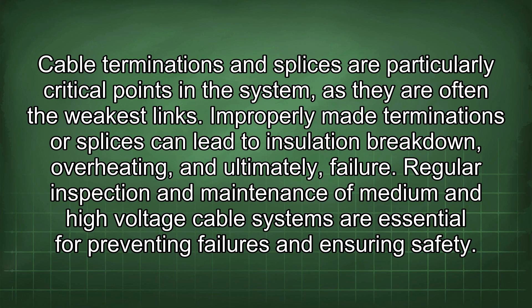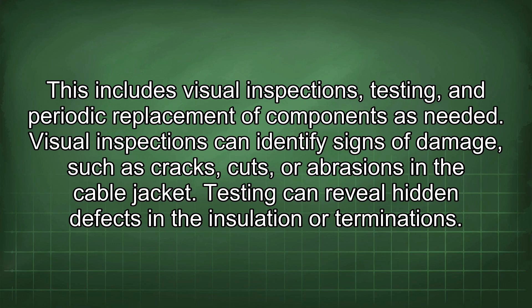Regular inspection and maintenance of medium and high voltage cable systems are essential for preventing failures and ensuring safety. This includes visual inspections, testing, and periodic replacement of components as needed. Visual inspections can identify signs of damage such as cracks, cuts, or abrasions in the cable jacket. Testing can reveal hidden defects in the insulation or terminations. Keeping accurate records of inspections, tests, and maintenance activities is crucial for tracking the condition of the cable system over time. This information can be used to identify trends, predict potential failures, and plan for future maintenance activities.